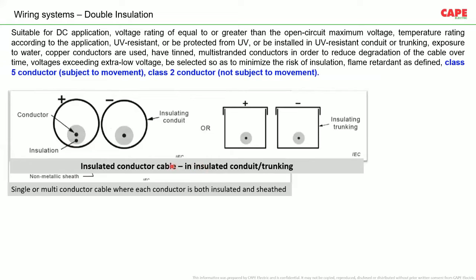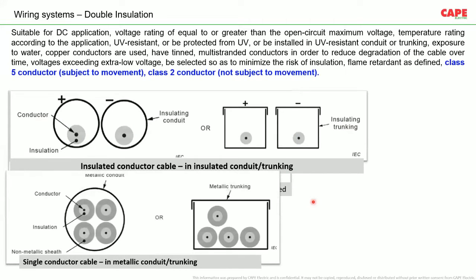If you use the normal copper wire which is available, you should use it inside a PVC or plastic conduit. Insulated conduits are required. So in this situation where I am moving the cursor, the wire has an insulation and is installed inside a PVC conduit, so you have two insulations, and the double insulation requirement is achieved. If you are putting it in a trunking, of course you should put it inside an insulated trunking. This also means on the DC side, a normal wire cannot be put in metallic cable trunking. It should be insulated trunking.